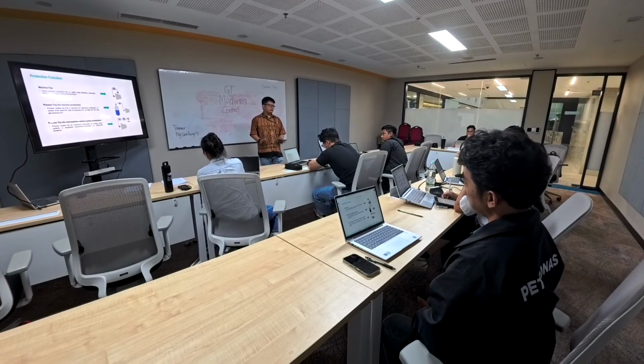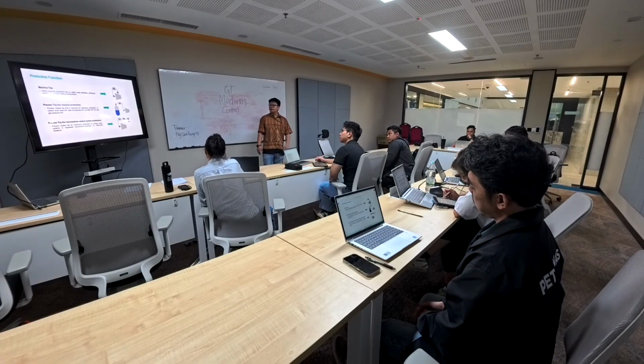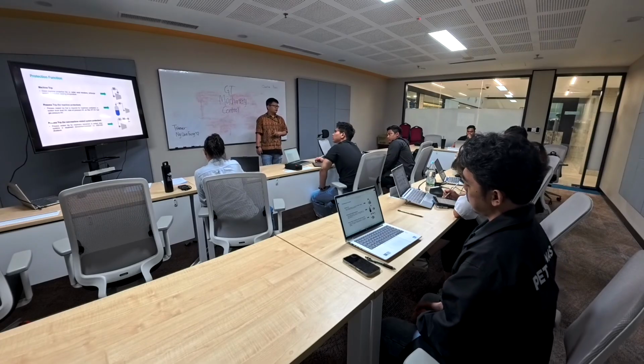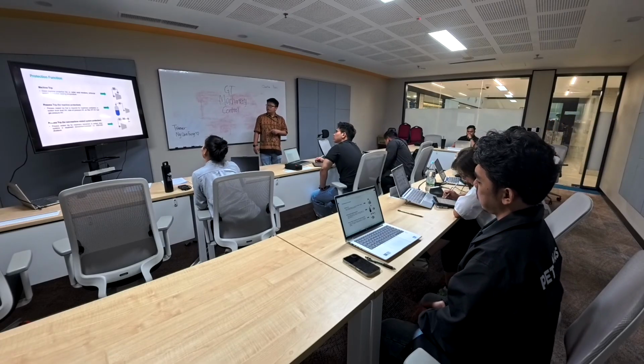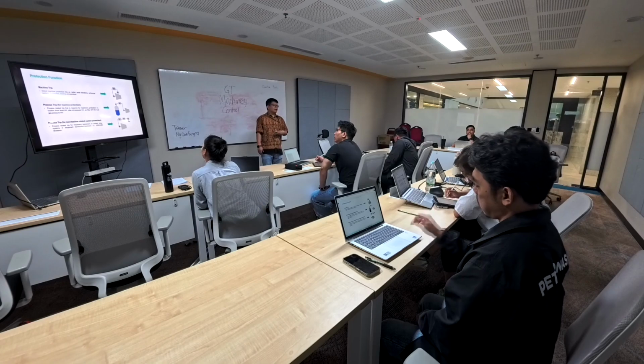And you also have non-machine related system protection process trip. That is, for example, an ESD button being pushed by the operator at the control room, and that has nothing to do with the machine. It has nothing to do with the train, for example the compression train or anything, but it's a process trip. So there are two types of process trip. One is directly related to the machine or the process. Another is related to the process but not related to the machine.